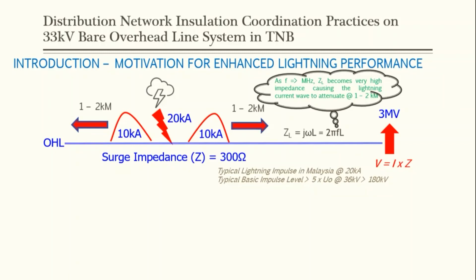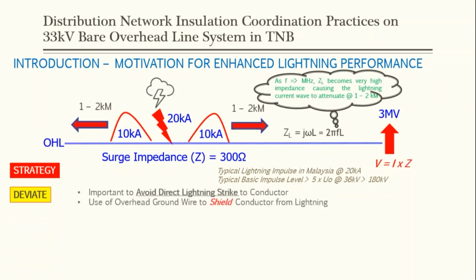Okay, so what is the strategy? First, we need to deviate the lightning strike. How can we do that? Because we won't be able to ask the lightning to hit places that we want the lightning to hit, right? We are not God, right? So what we can do is try to avoid direct lightning strikes to the conductor, using overhead ground wire to shield the conductor from the lightning. Okay, so in that way, the lightning will not hit directly on the conductor.